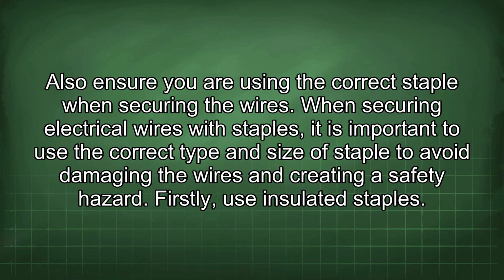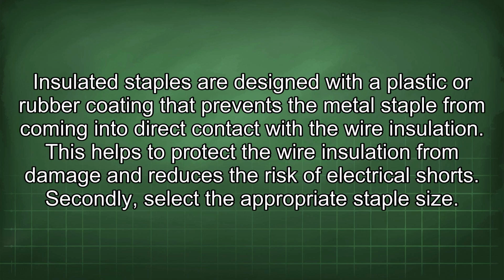Also ensure you are using the correct staple when securing the wires. When securing electrical wires with staples, it is important to use the correct type and size of staple to avoid damaging the wires and creating a safety hazard. Firstly, use insulated staples. Insulated staples are designed with a plastic or rubber coating that prevents the metal staple from coming into direct contact with the wire insulation. This helps to protect the wire insulation from damage and reduces the risk of electrical shorts.